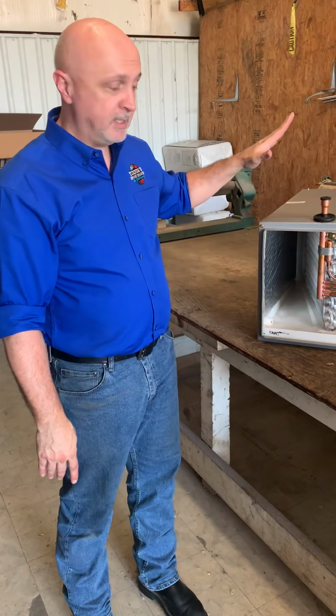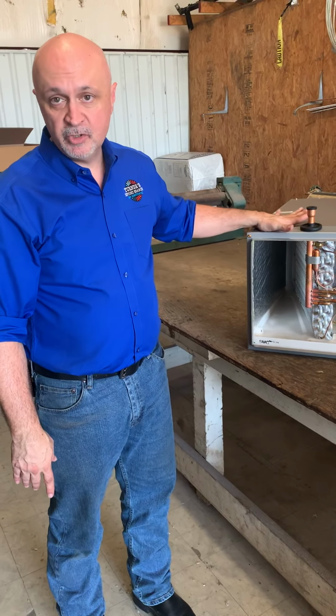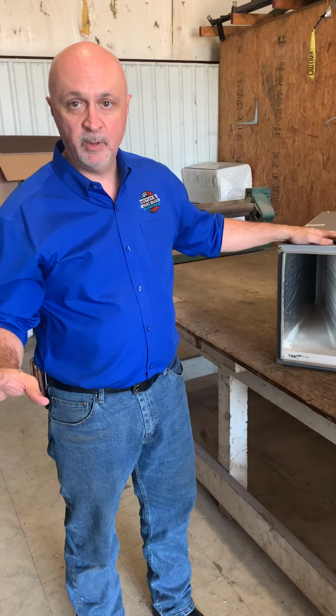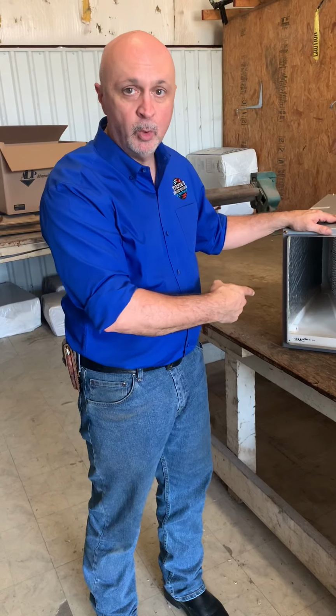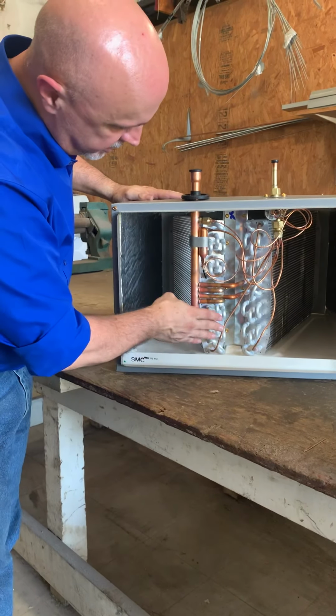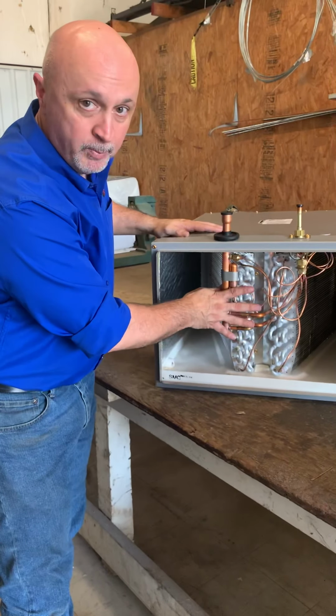I wanted to talk to you today about evaporator coils and how they have changed dramatically up in the attic space. First and foremost, the biggest thing that's been happening with evaporator coils in the past is that when they are 3 to 5 years old, a technician comes and says you're low on refrigerant and your evaporator coil is leaking. Here's why. If you see this coil, 98% of all of the tubing that you see is all aluminum. This is new. It used to all be copper.